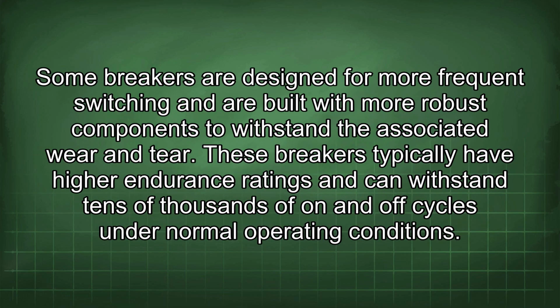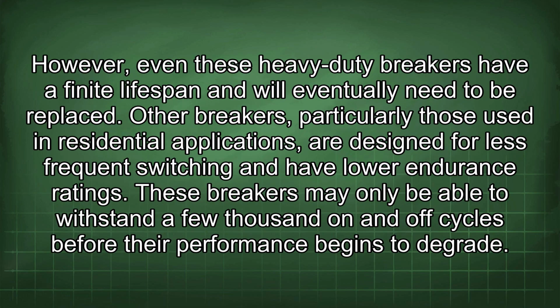failure. Some breakers are designed for more frequent switching and are built with more robust components to withstand the associated wear and tear. These breakers typically have higher endurance ratings and can withstand tens of thousands of on and off cycles under normal operating conditions. However, even these heavy-duty breakers have a finite lifespan and will eventually need to be replaced. Other breakers, particularly those used in residential applications, are designed for less frequent switching and have lower endurance ratings.